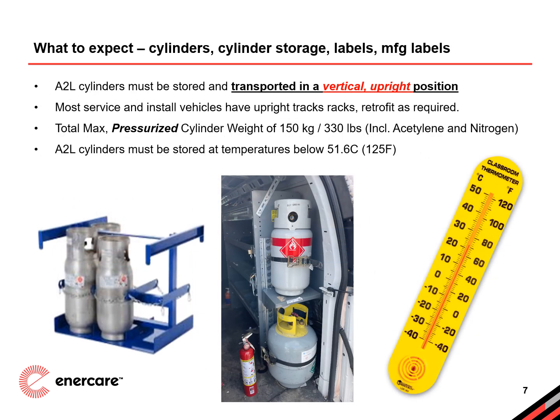When working with A2L refrigerant cylinders, proper storage and transportation are critical for safety and TDG compliance. Here are a few key points to remember. First, A2L cylinders must always be stored and transported in a vertical upright position. This is to ensure the vapor phase of the refrigerant is at the safety device and the safety valves function as intended while preventing any accidental release of liquid refrigerant.